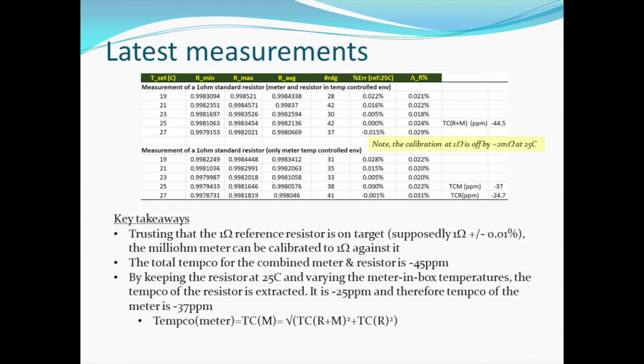Basically only the meter is kept in the temperature control environment, so this is checking the effect of temperature on the meter, not on the resistor. So the resistor is at ambient temperature at around 25 Celsius, so this tells you how much the meter itself is moving around with respect to temperature. The key takeaway is that if I assume that the 1 ohm resistor is on target, which I think it should be, it's a very accurate 1 ohm plus minus 0.01%, then I can calibrate this meter against it at 1 ohm. I just need to account for that 2 milliohm variation, which I can calibrate out in the future.